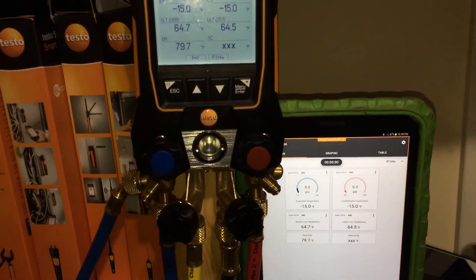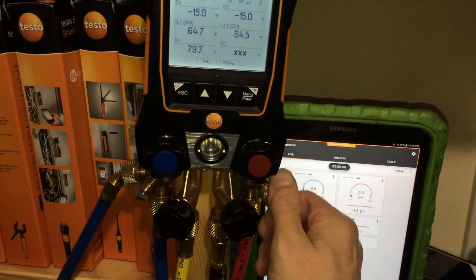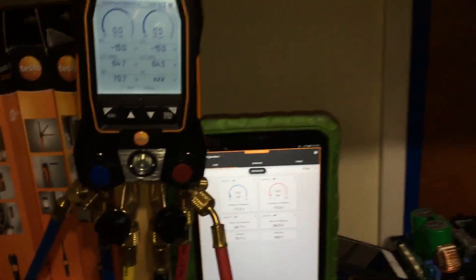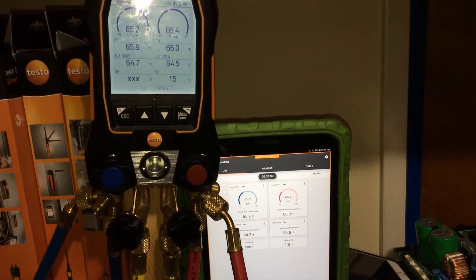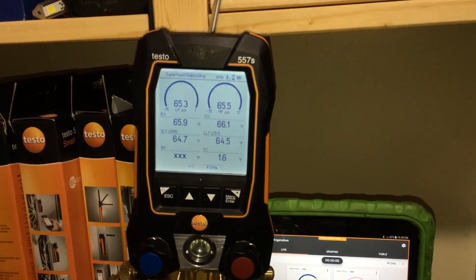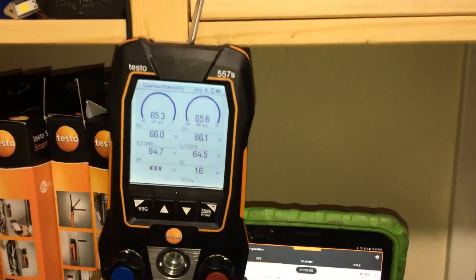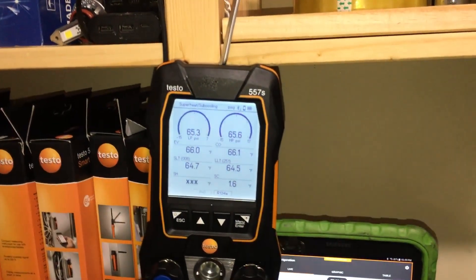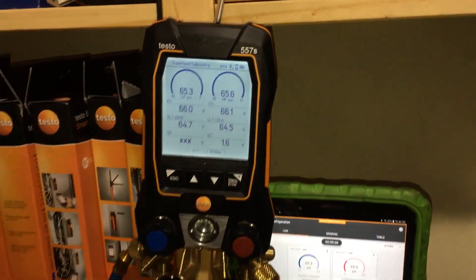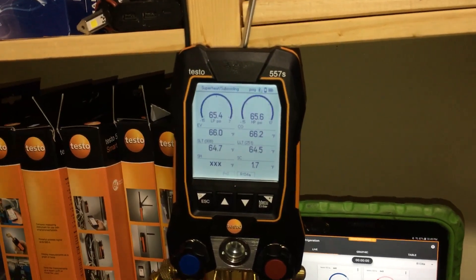We can see both of them. Let me open some pressure. I'll shut that off so we can watch the high and low side go up. There we go — we just went up. We are at 65.4 PSI, and it changed here and here. So you can guess what the temperature is in my little workroom. If this is R134 and it's 65.4 PSI, you use your PT chart and you know exactly what temperature it is. Actually, that was out in my car — it would be roughly 68–69 PSI in my room for my temperature right now.